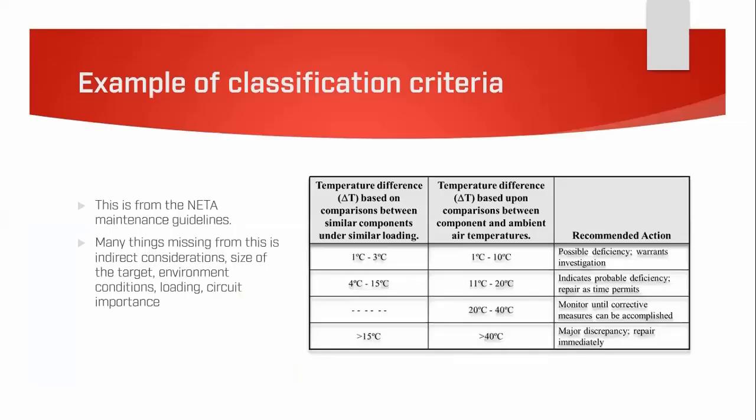This is an example from the National Electric Testing Association — an American classification criteria. Looking at it: 1–3°C delta T on a similar component is a possible deficiency, warrants investigation. 4–15°C indicates probable deficiency, repair as time permits. Anything above 15°C is a major discrepancy — repair immediately. Note that some things are missing from this standard, such as indirect considerations, target size, environmental conditions, loading, and circuit importance.